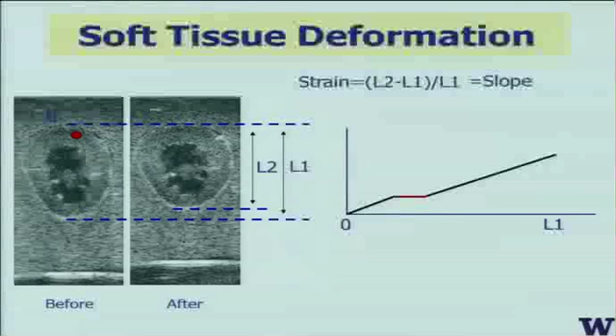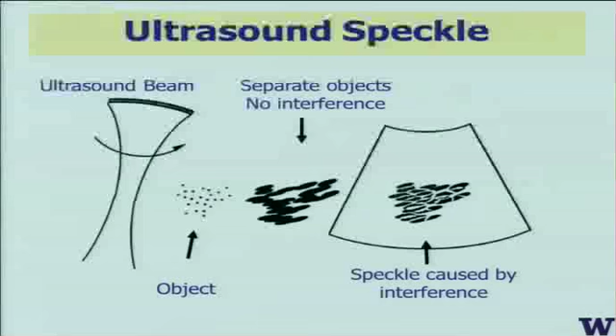So if microstructure moves, you can use that speckle characteristic to track how that microstructure has moved. So it's actually an ideal target for being able to do tracking. And so that's what happens in an ultrasound system: you have this microstructure which interacts with the ultrasound beam, presents the speckle, and the speckle is caused by interference. But it's a structure. That interference pattern is directly related to the original structure, and as that structure moves, so too does the speckle move. And so when you do that, let's go to the simple example that I had before.